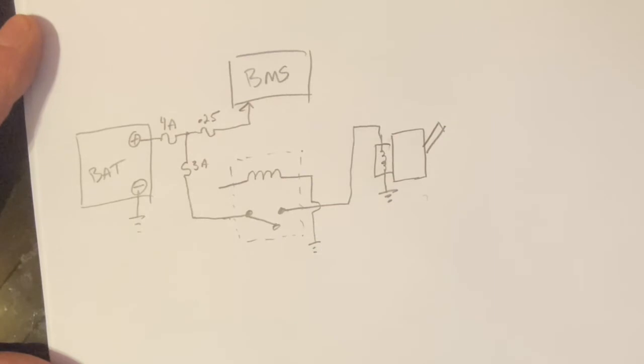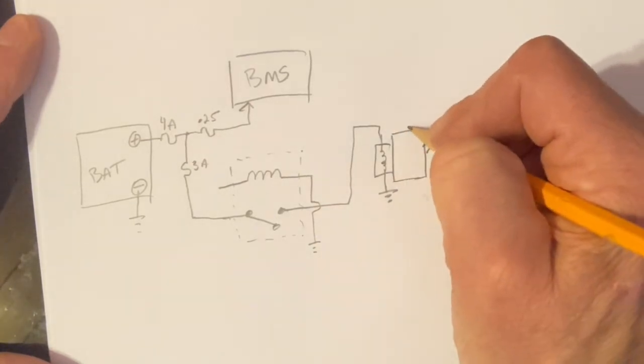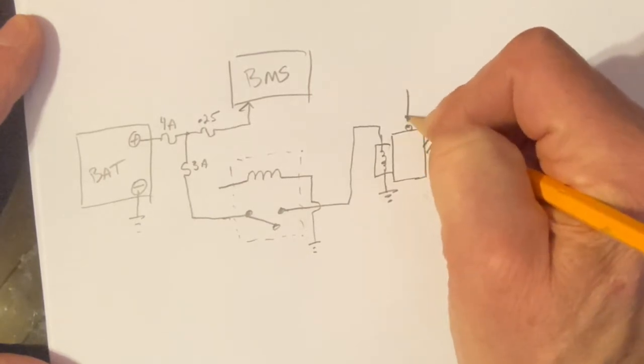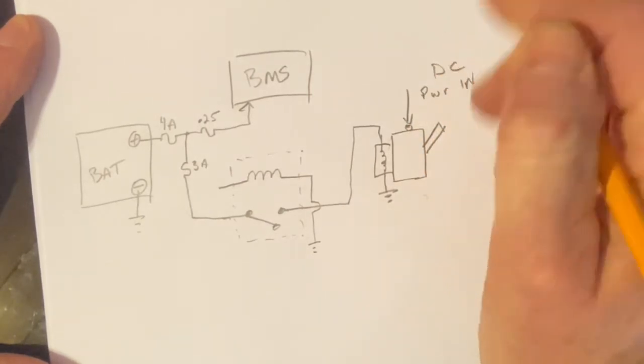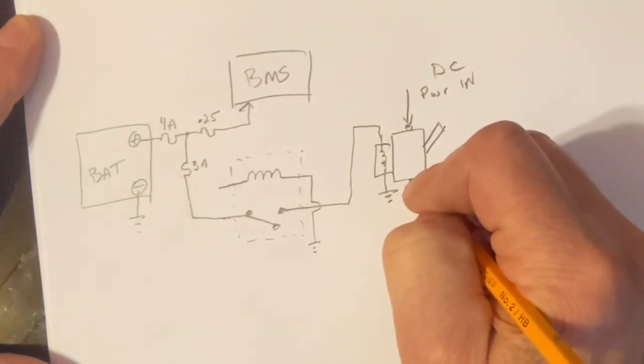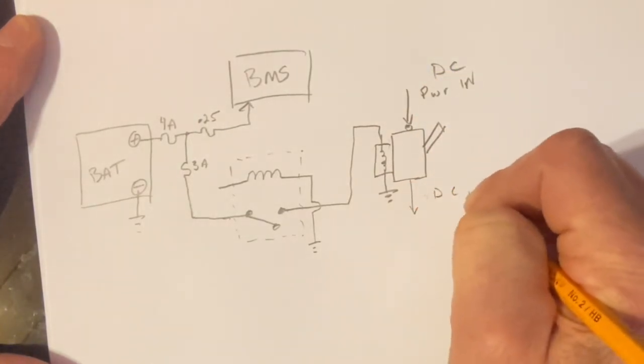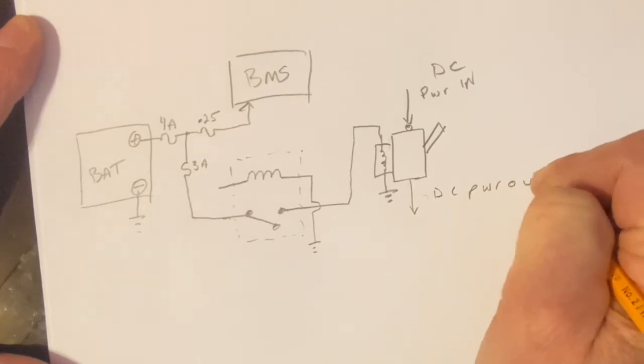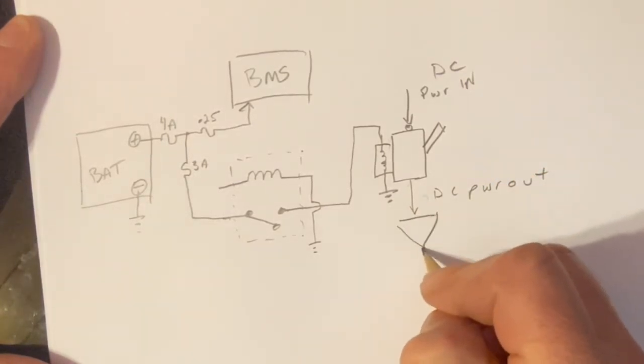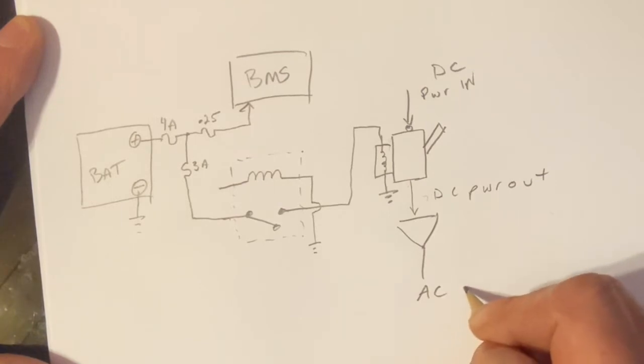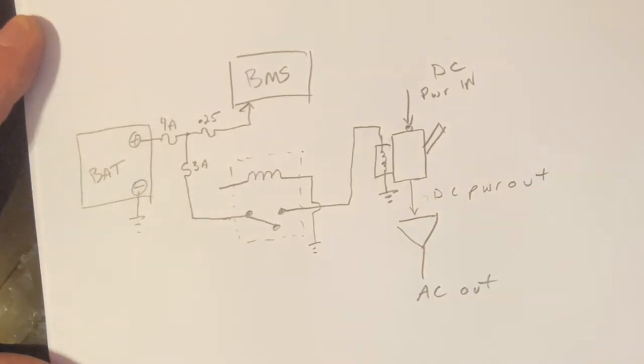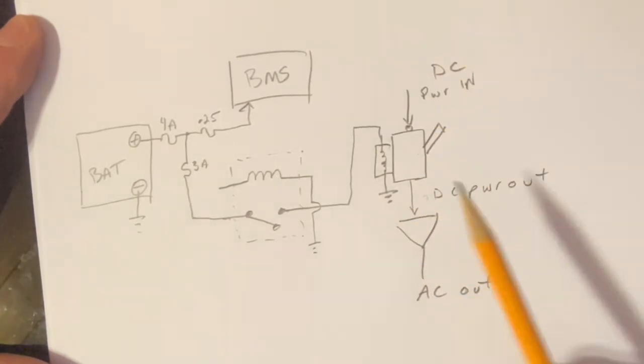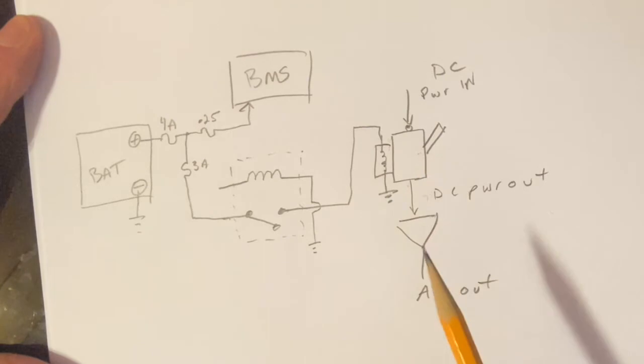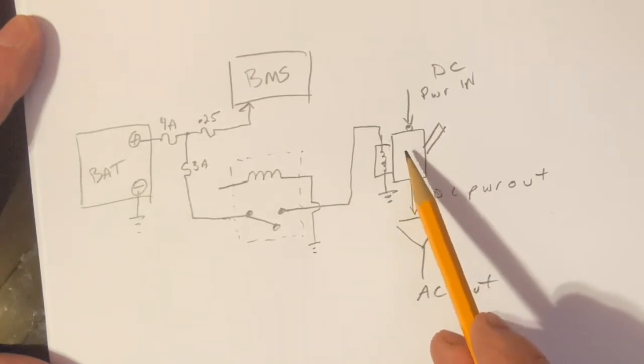Let's use an example of if the voltage gets too high, we want to shut off the power in. This is our main DC power in, and this would be our DC power out to the inverter, which gives our AC out. Okay, so under normal circumstances, everything is flowing as it should be. When this coil is activated, it trips the breaker and turns off the power.